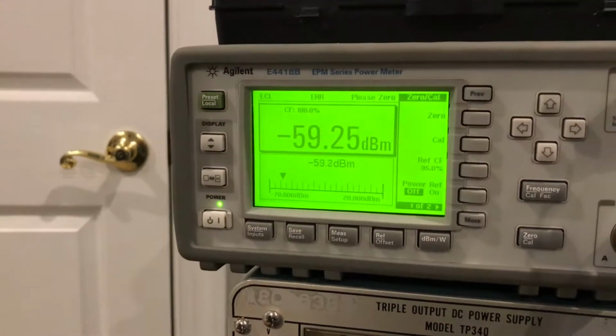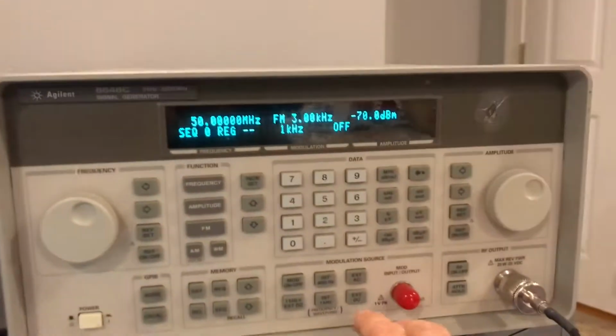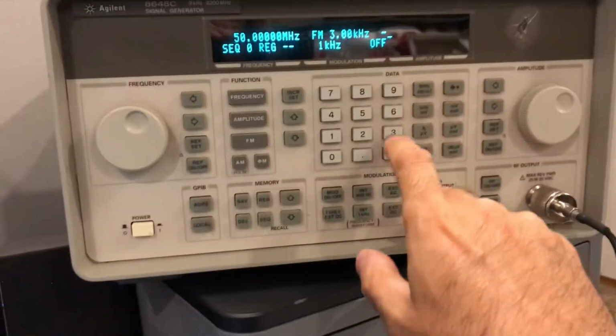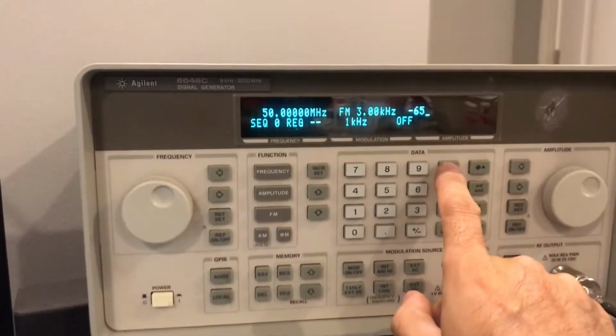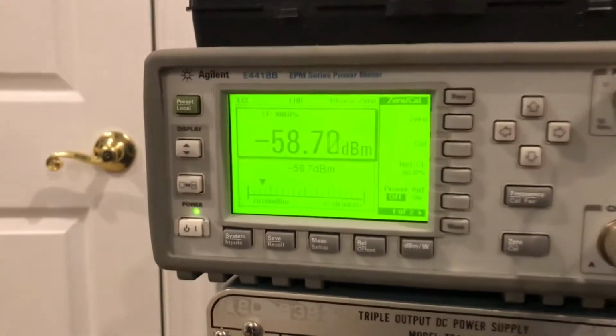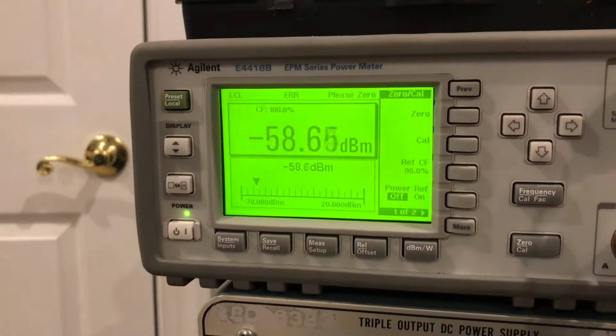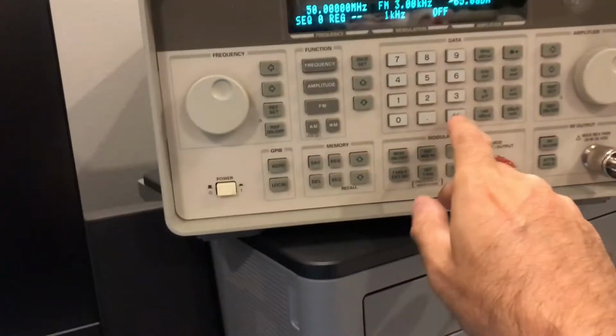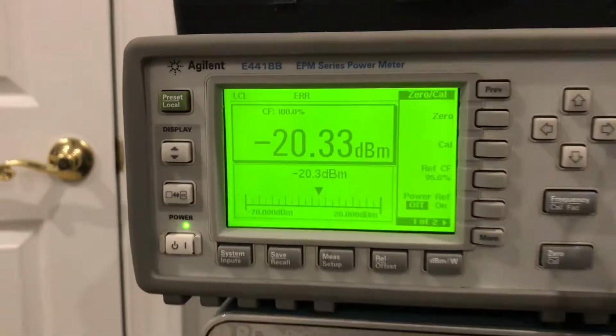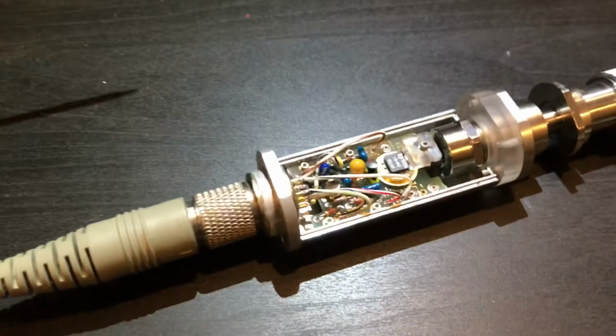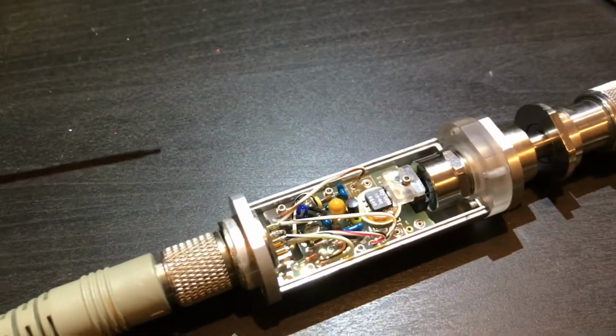We'll go ahead and put it there at minus 70 dB, and we're getting about a minus 59. Now, when this sensor was fully working, about the best I could get reliably was about a minus 65 dB on the signal. And of course we're not getting that either. Now we're getting minus 58.6 dB. So let's go back here to minus 20 dB, and we're back at our minus 20 dB. So it's interesting that we can't cal and we can't zero, but for some reason the signal seems to be working.